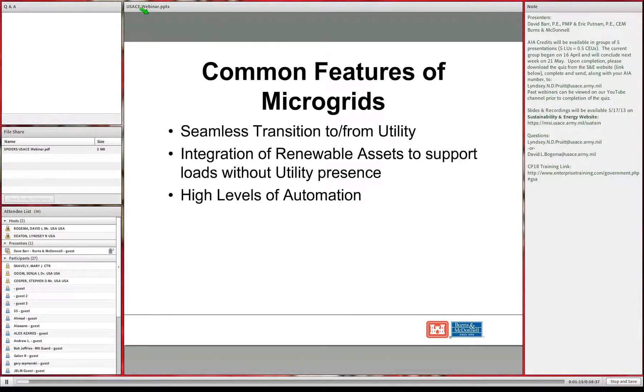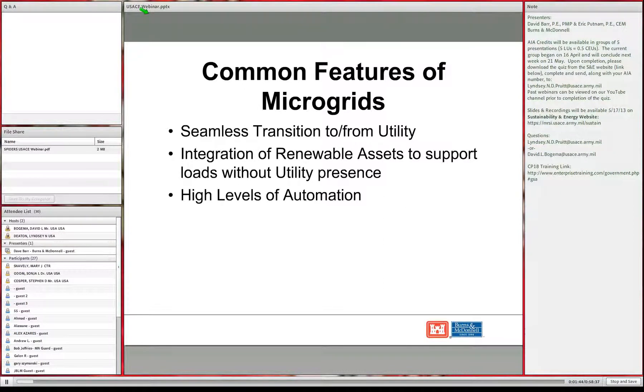Common features of a microgrid include seamless transition to and from the utility. If a utility outage is coming or there's instability and you want to go into islanded operation mode, you should be able to do so without taking a power outage. Similarly, even if you go into microgrid configuration due to an unanticipated loss of utility, you don't want to take a second outage when transitioning back to standard utility supply.